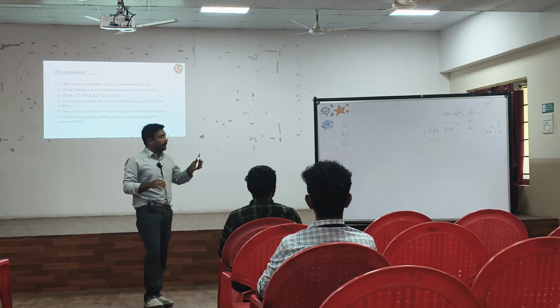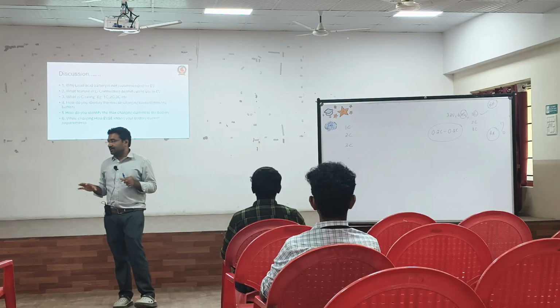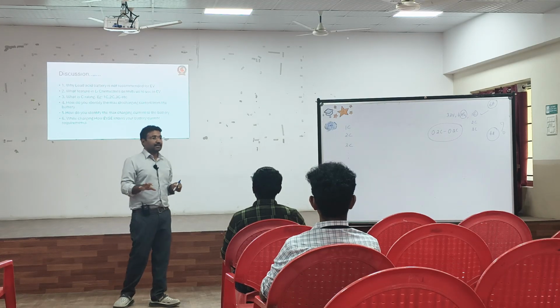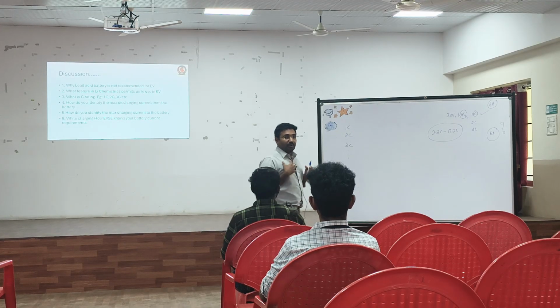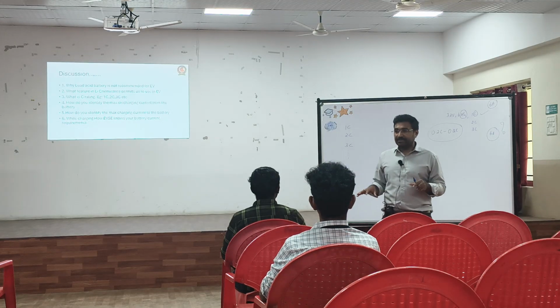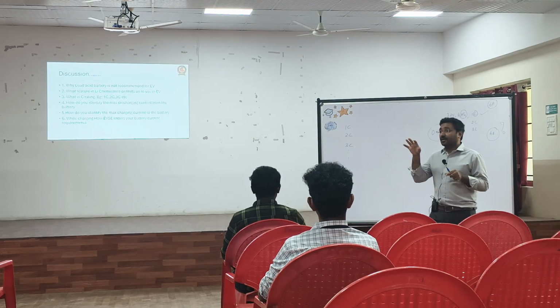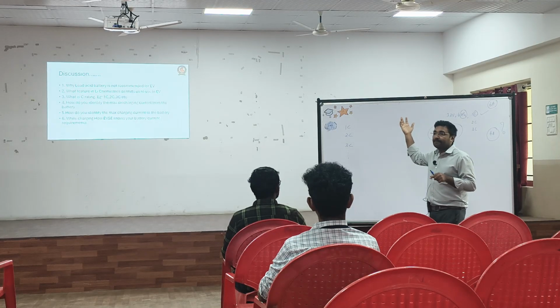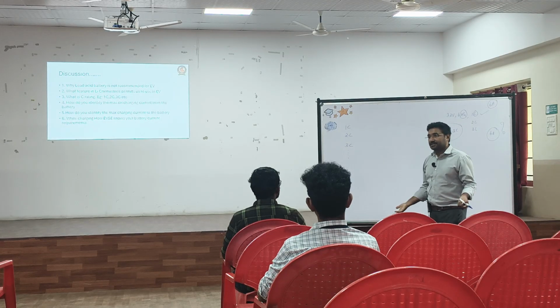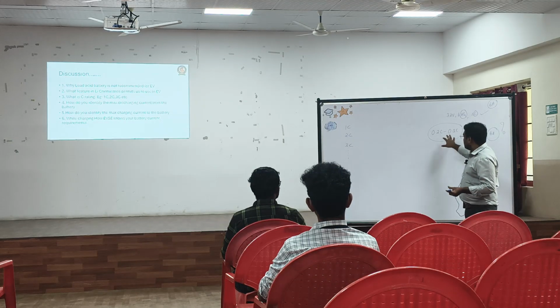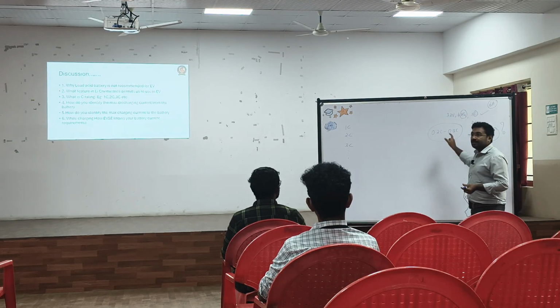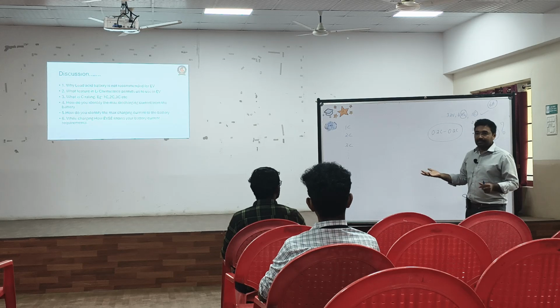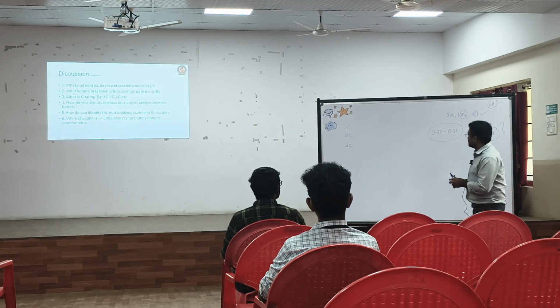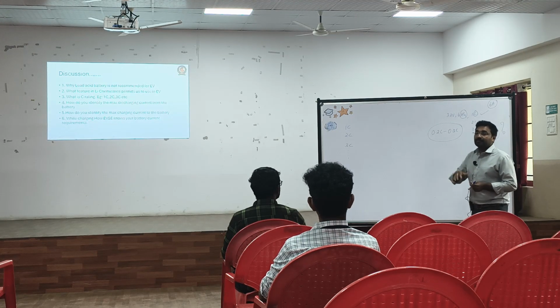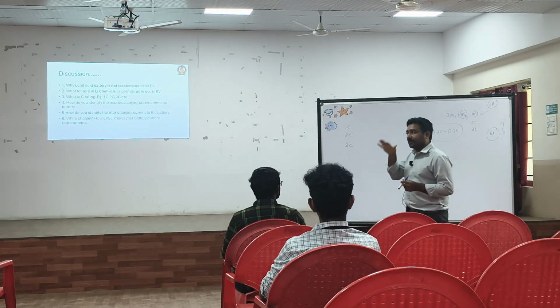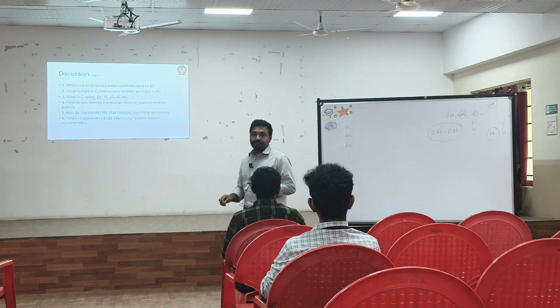Is it clear? So I come back again: the C rating you see on the sticker is for discharging rate, not charging rate. But if I want to know the charging rate, I have to refer to the data sheet. If the data sheet is not specified, or you are not able to get it - sometimes we buy from China and after getting the cell, people tell us there is no data sheet at all - then we have to take a thumb rule saying 0.2C to 0.3C is the top. You can test it. If you want, you can test with a higher C rating also. I have tested up to 0.5C for some cells. But you have to test many cells, many number of times, to come to a conclusion.